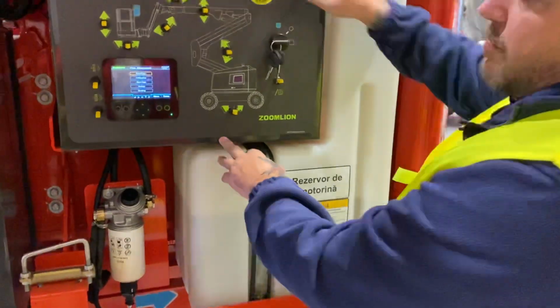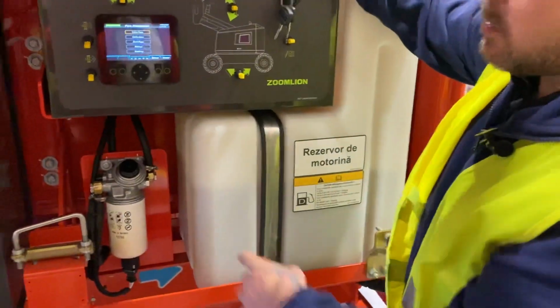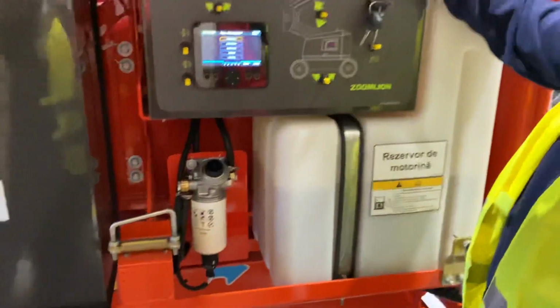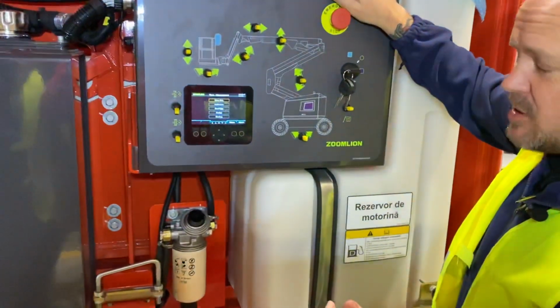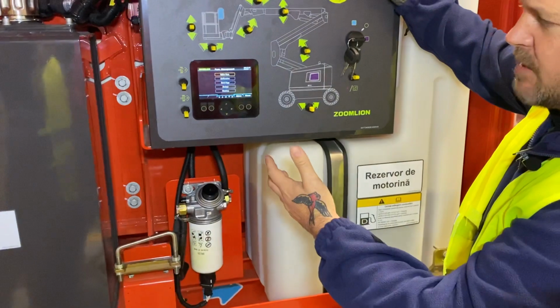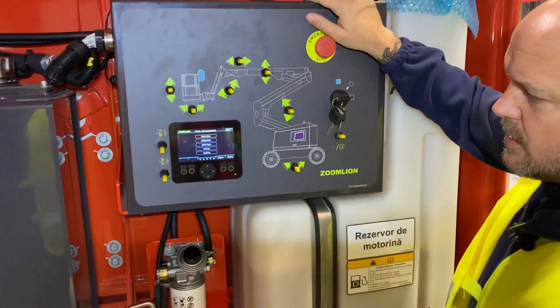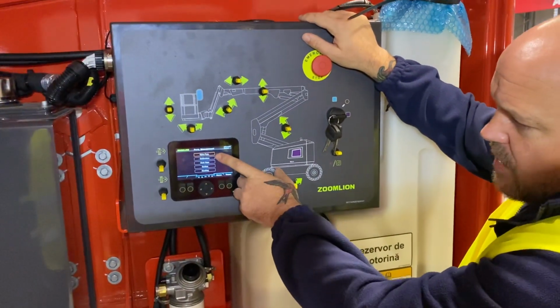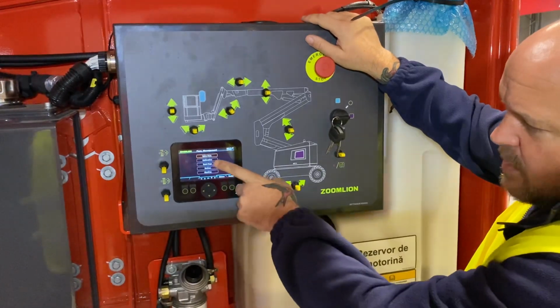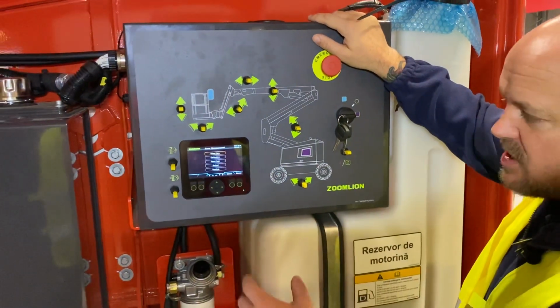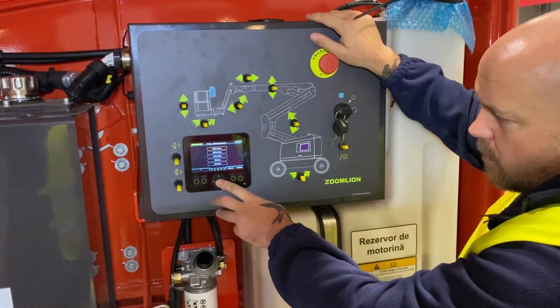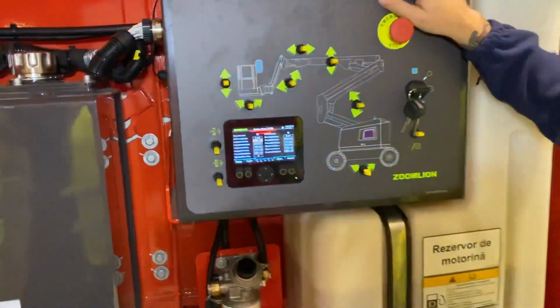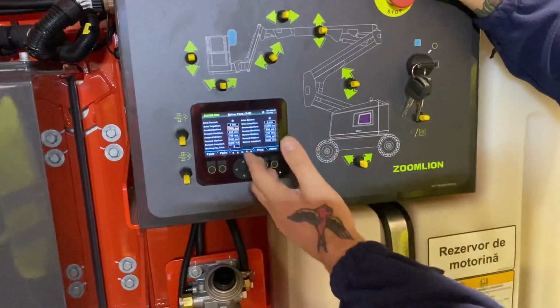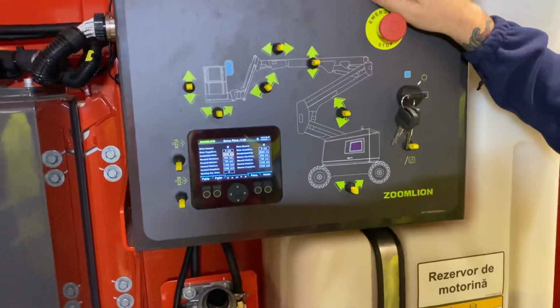Okay, so now we're in the parameter management page, okay? If this was an electric machine, underneath valve parameters, you would say motor pump parameters. But obviously this doesn't have a motor pump parameter because it's a diesel machine. So the two that we're interested in is valve parameters and calibration. If I was to enter calibration now, I'd have to enter a separate password for that. But first we'll look at valve parameters, okay? So the red message is just to say you've successfully entered that menu, okay?